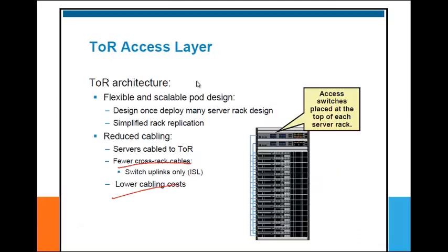The end of rack is like this. Okay, one more thing here about top of rack. Though it minimizes the cabling complexity, it adds management complexity and power and cooling cost. Why? We have additional two boxes, so management complexity is increased, and additional power and an additional cooling system are needed. So that's the other side of top of rack.